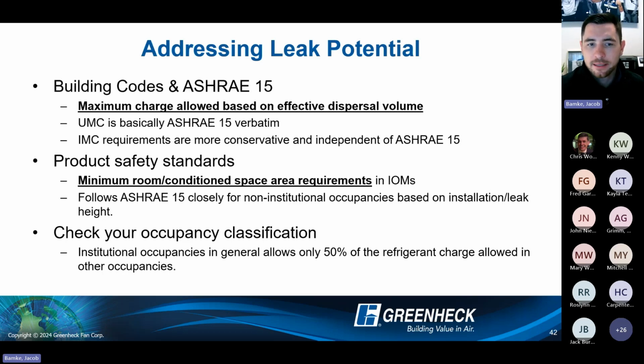And then you get into the product safety standards piece. There are minimum room or conditioned space area requirements. And typically that's going to have to be provided in all of the manufacturer IOMs. So we are including that in our IOMs. This does follow ASHRAE 15 closely for non-institutional occupancies based on where you install it and then the leak height as well. And we'll cover some of that as well. And then the biggest thing is check your occupancy classification, because institutional occupancies in general allow 50% of the refrigerant charge that other occupancies may allow as part of these tables. So it's a little bit more strict if you're designing around those institutional occupancy designations.